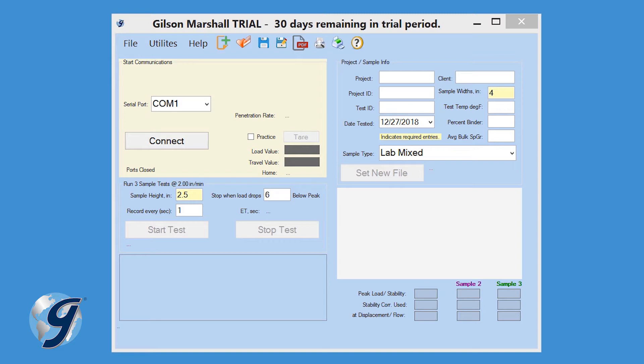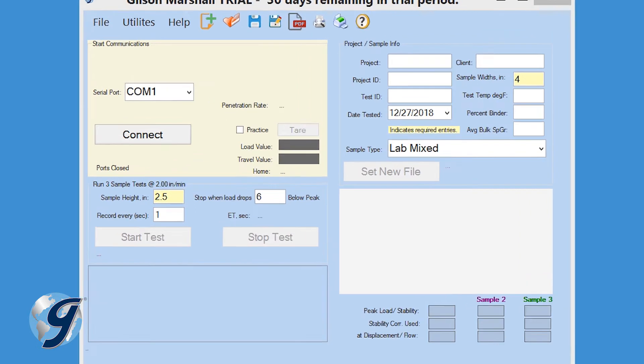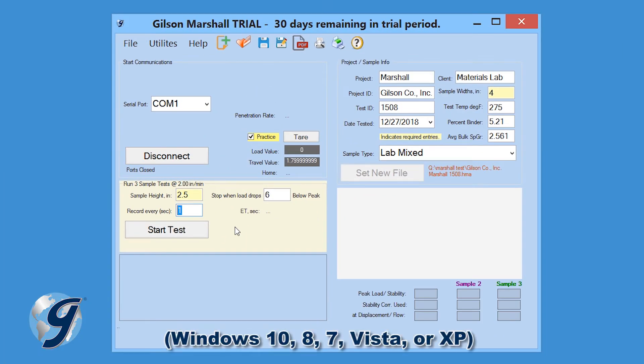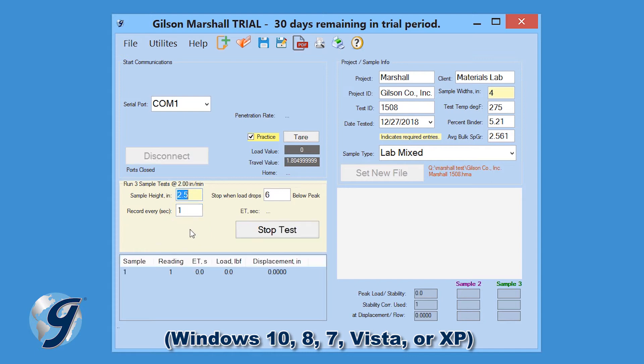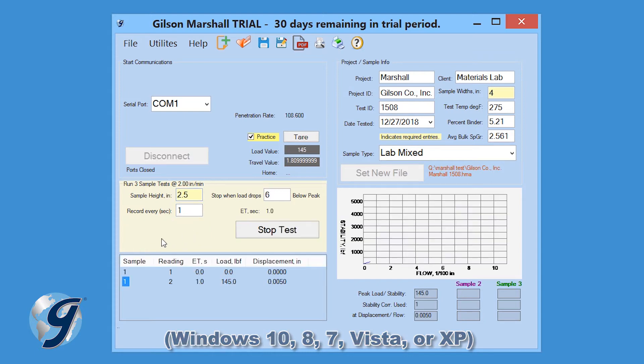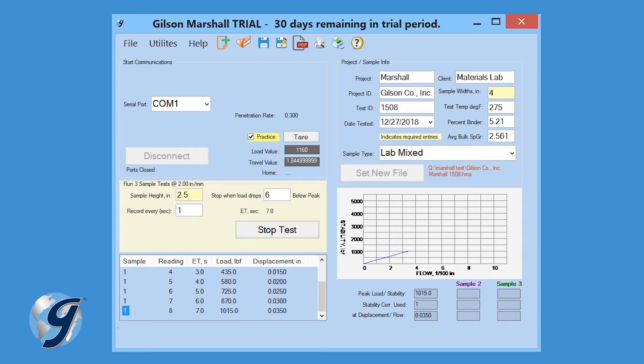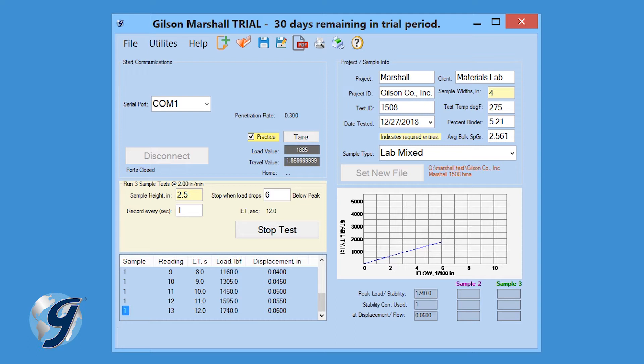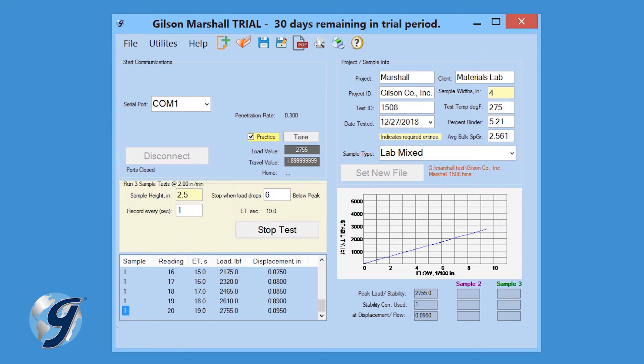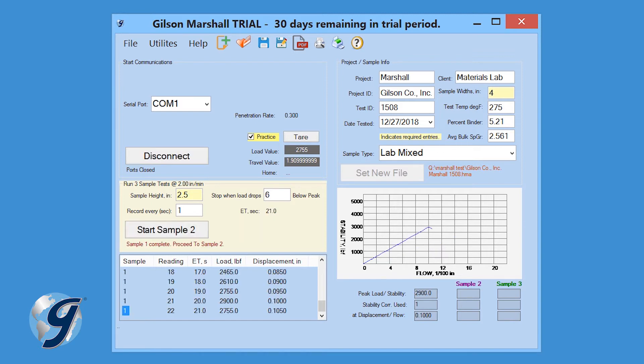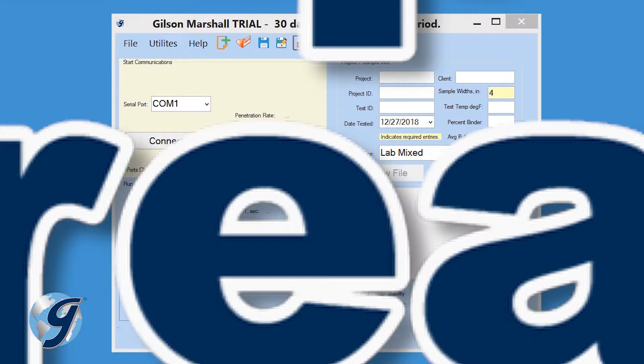The Gilson Marshall Stability and Flow Data Acquisition Software is an intuitive, easy-to-use, Windows-based program that records and graphs the maximum load and total displacement of the test specimen during loading. Test results are automatically calculated in accordance with ASTM and AASHTO standards. Three tested samples are included within a single data file, and test results can be printed in a customizable PDF and easily exported into spreadsheet applications such as Excel.